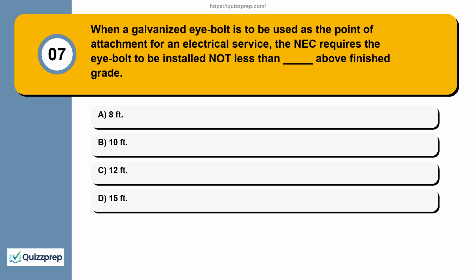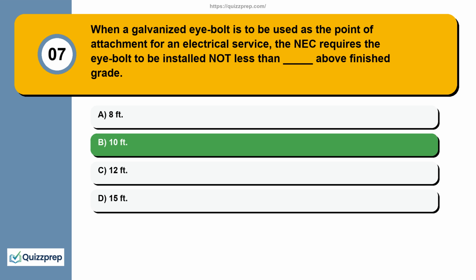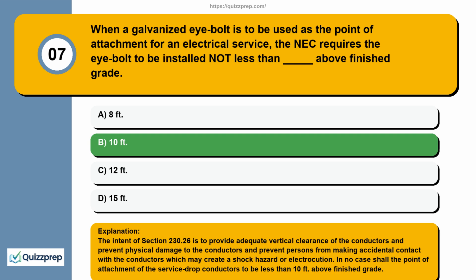Question 7. When a galvanized eye-bolt is to be used as the point of attachment for an electrical service, the NEC requires the eye-bolt to be installed not less than above finished grade, 8 feet, 10 feet, 12 feet, 15 feet. The intent of section 230.26 is to provide adequate vertical clearance of the conductors and prevent physical damage to the conductors and prevent persons from making accidental contact with the conductors, which may create a shock hazard or electrocution. In no case shall the point of attachment of the service drop conductors be less than 10 feet above finished grade.